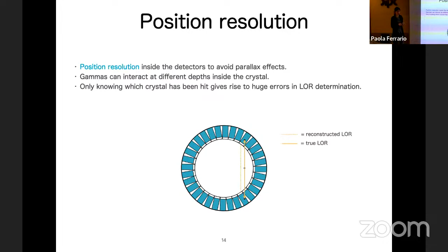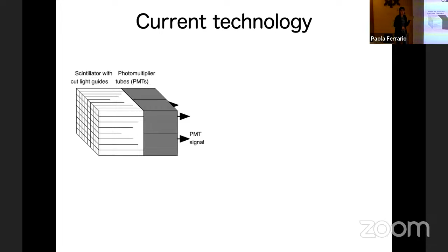The current technology, as I mentioned before, uses crystals. You have to imagine crystals a few centimeters long and a few millimeters square in area. These crystals are usually coupled in blocks to photosensors, either photomultiplier tubes or silicon photomultipliers, which I will talk about later. So when a photon enters your crystal, it interacts, and scintillation light is produced: secondary photons, usually in the blue range of wavelength, which are detected by these photosensors. And so you can detect the energy, the position, and so on.